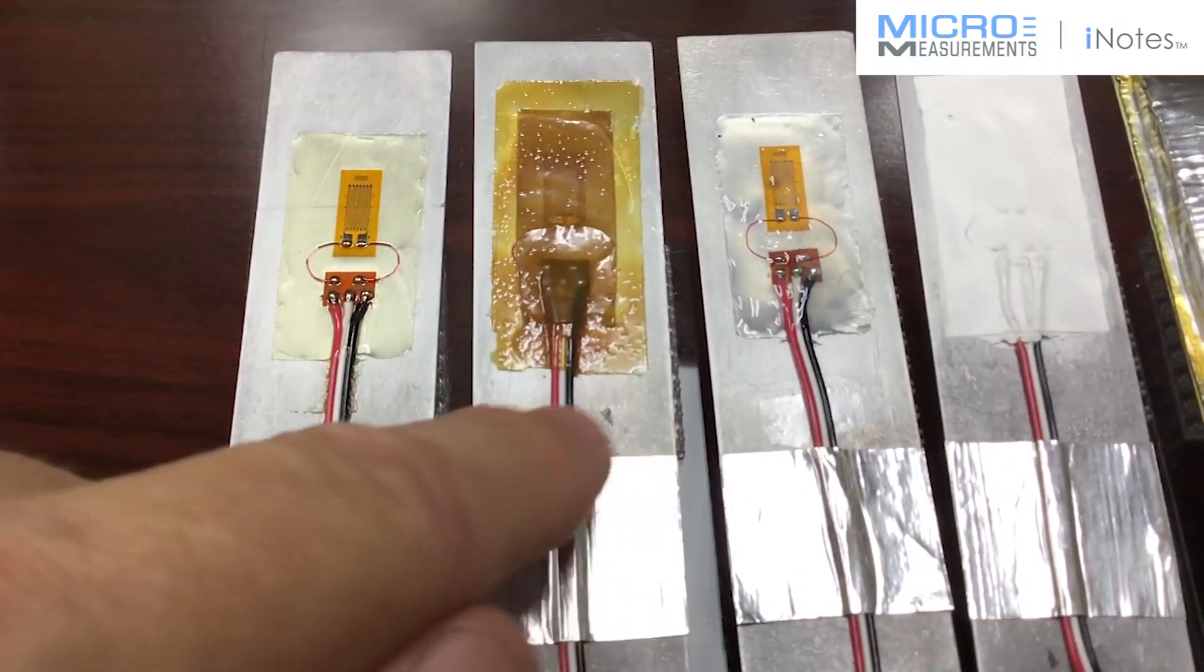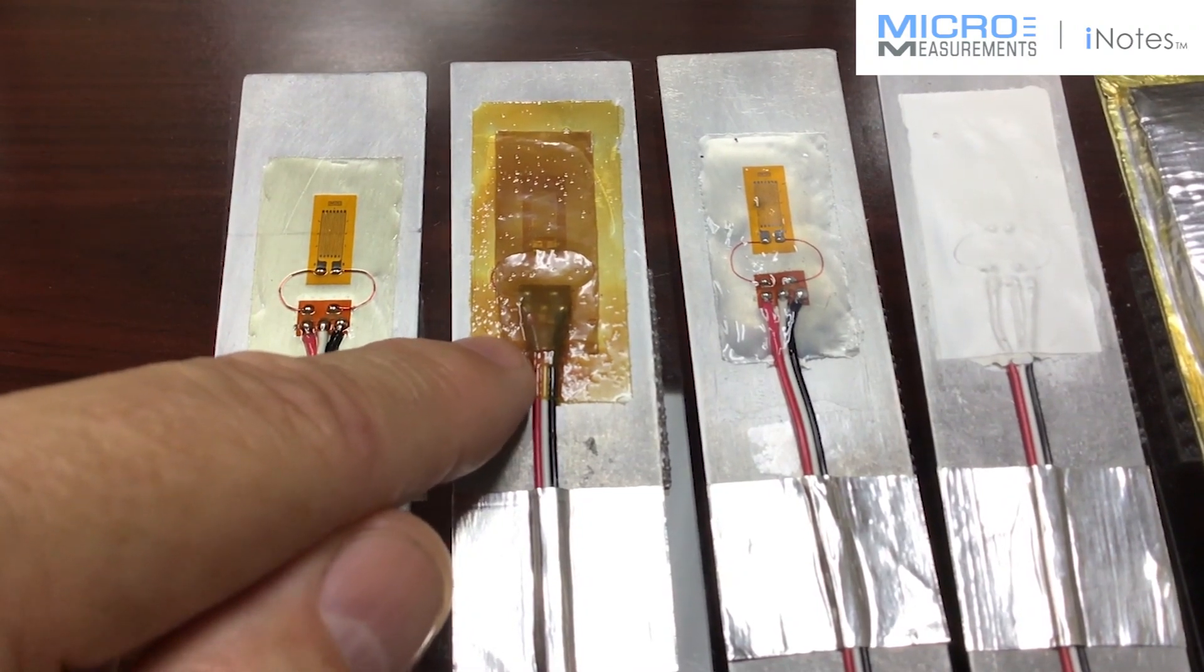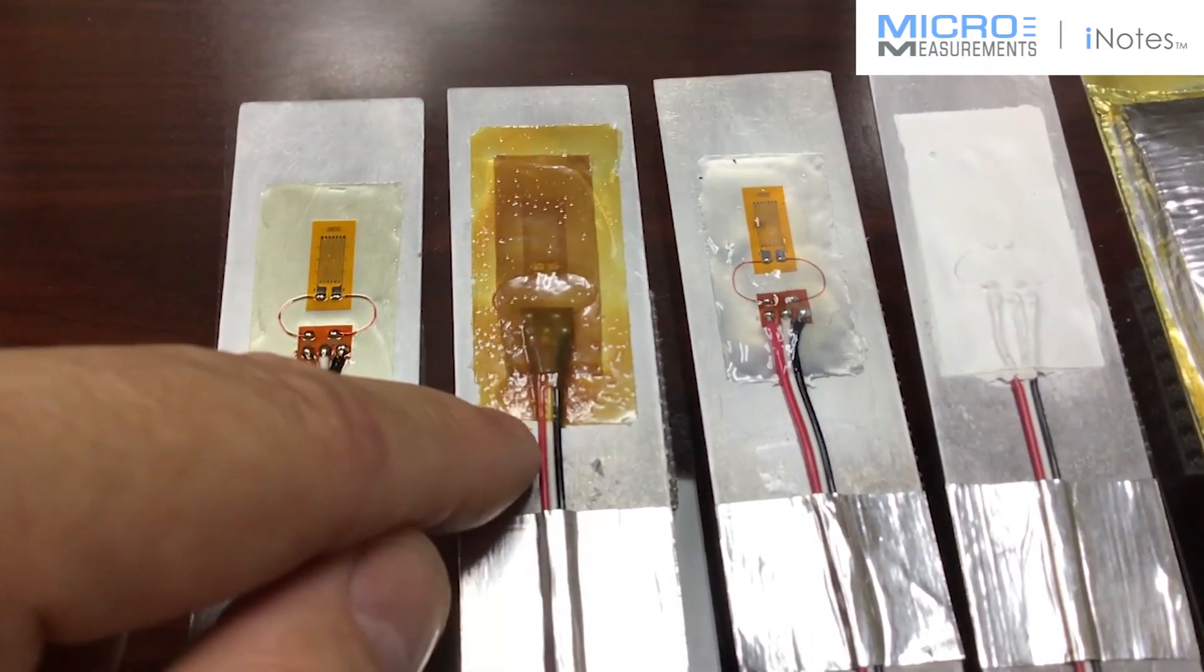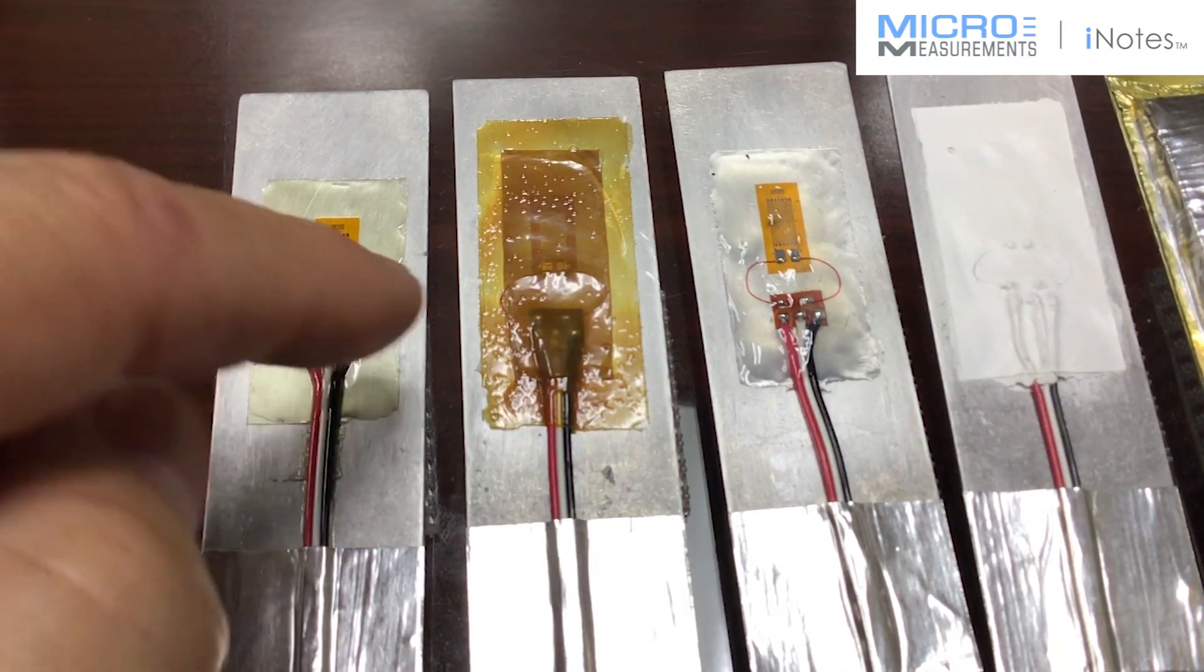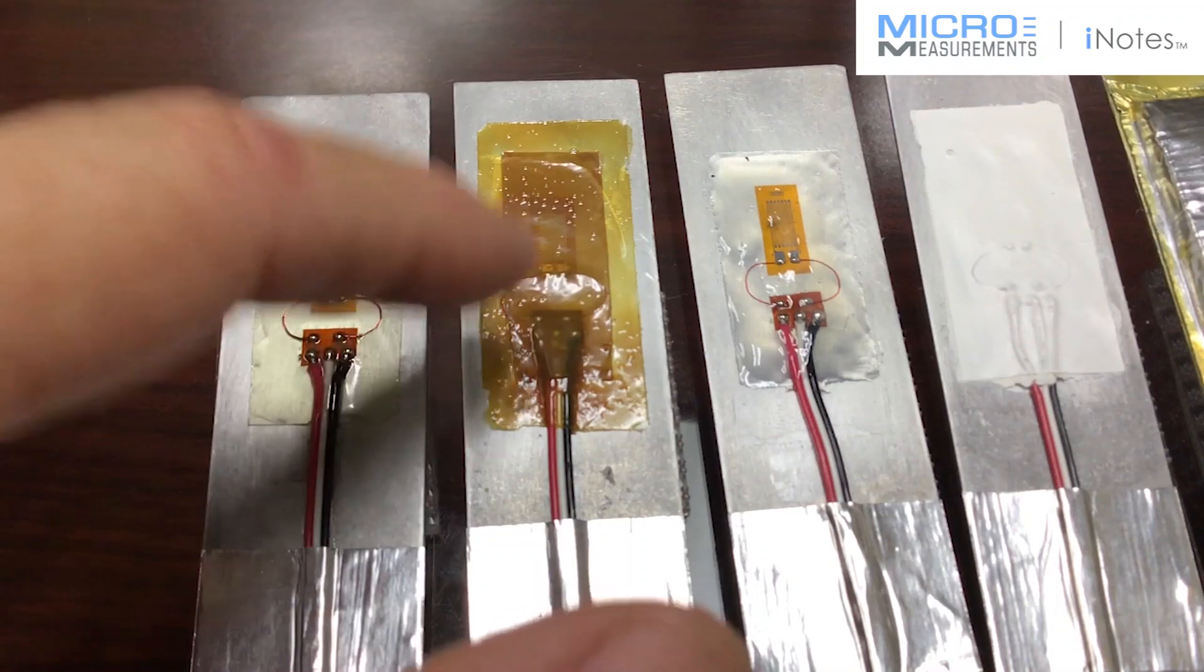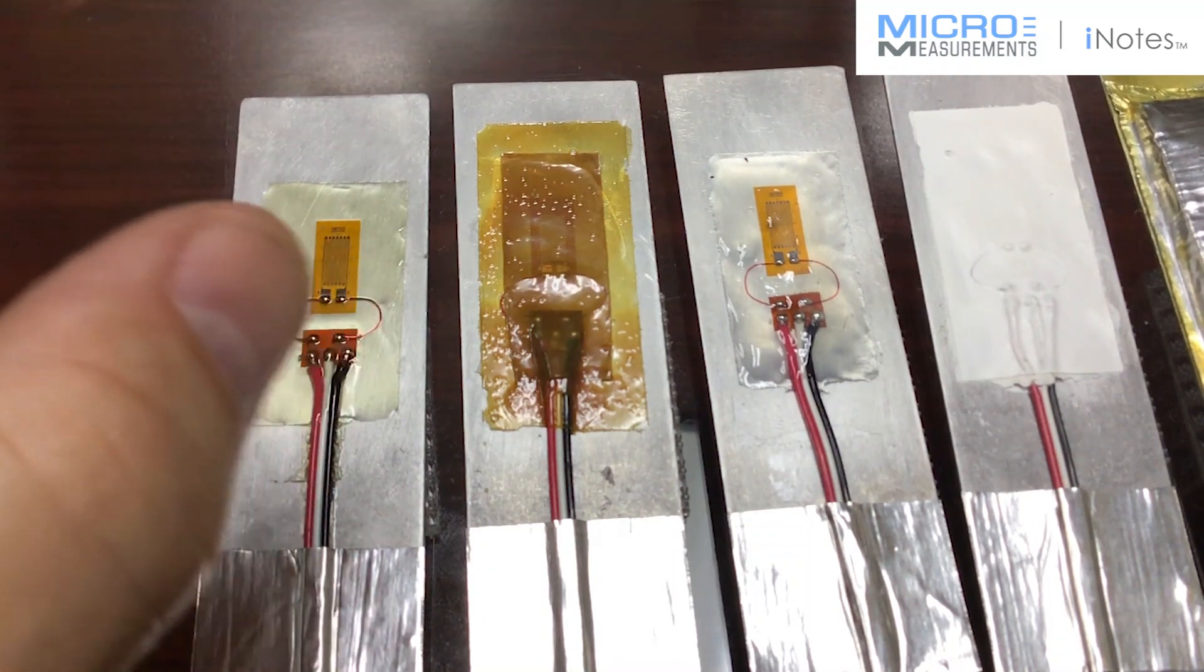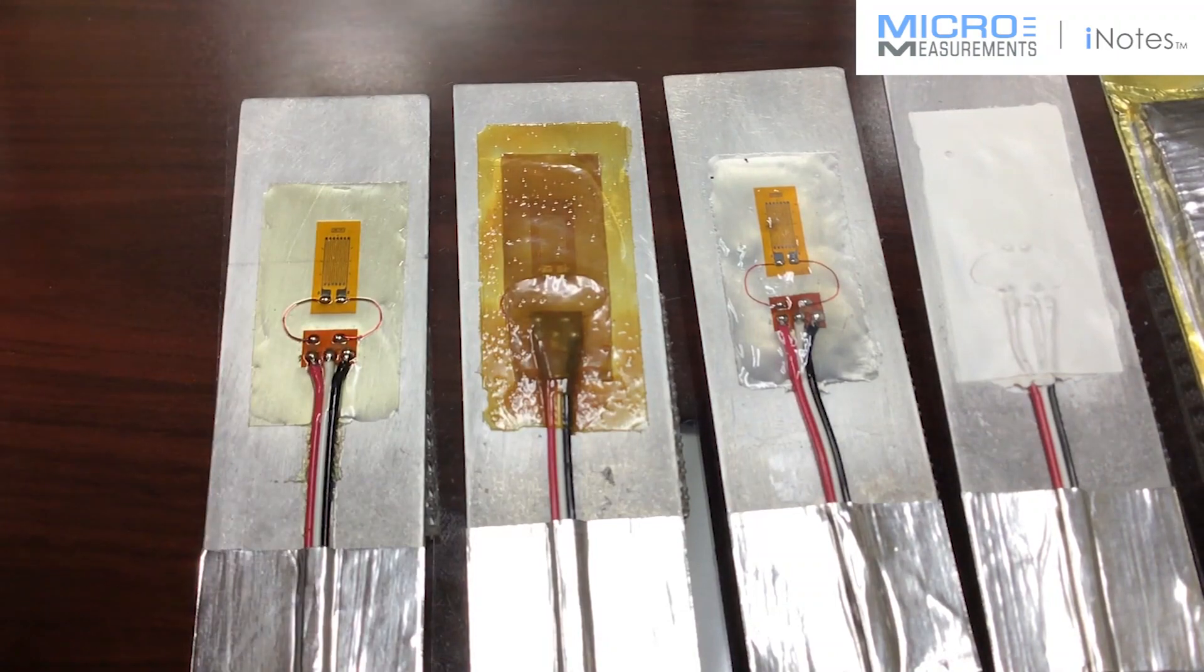The next one is our M-Coat B. M-Coat B is a single part nitrile rubber that you apply over top of the strain gauges, and oftentimes you apply it over top of other environmental coatings as well. This will help to enhance the moisture protection as well as the chemical resistance of coatings such as maybe a wax coating or some of the other coatings like M-Coat D.